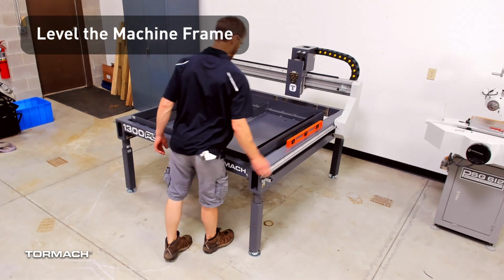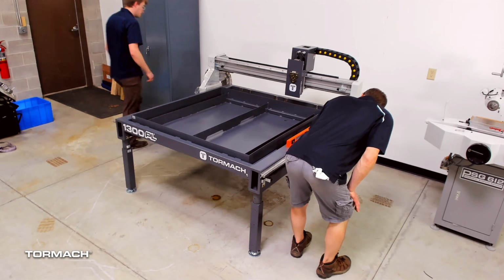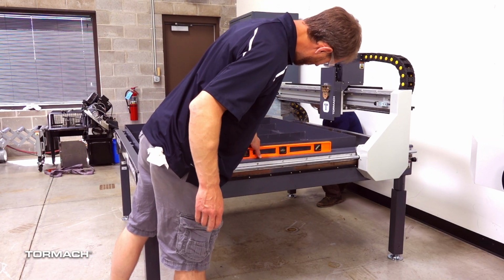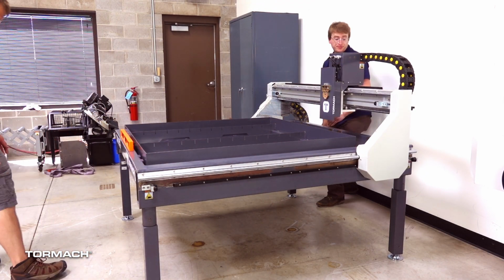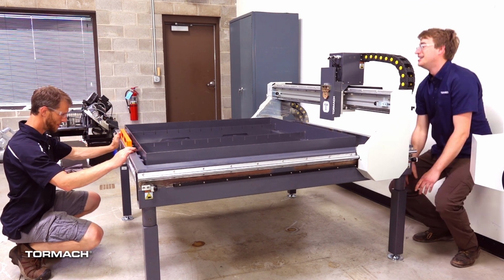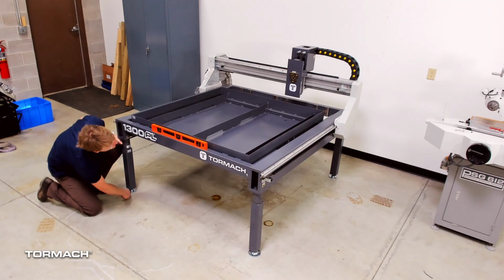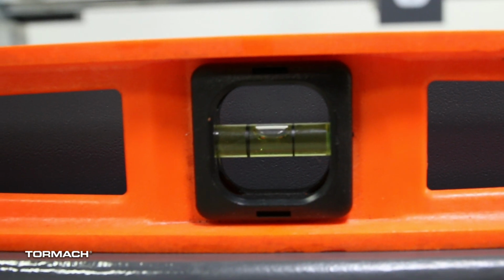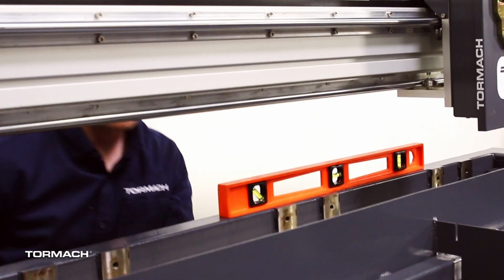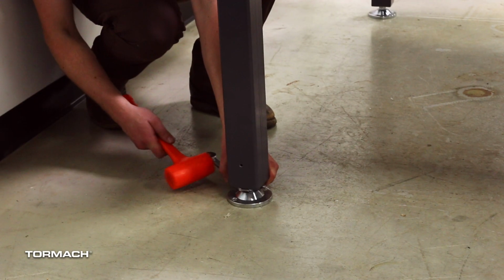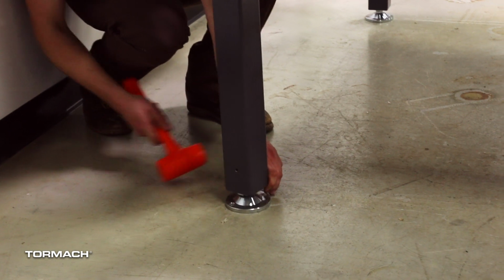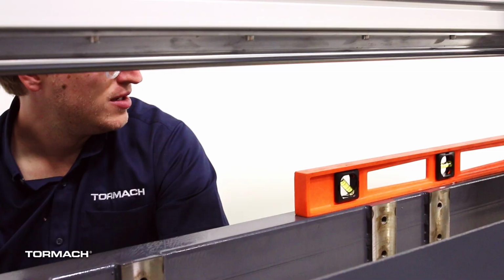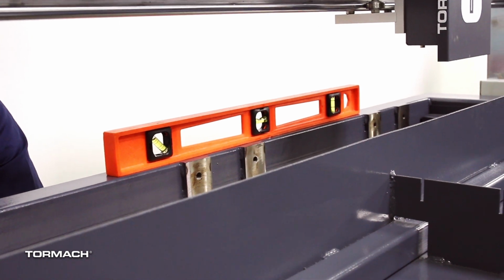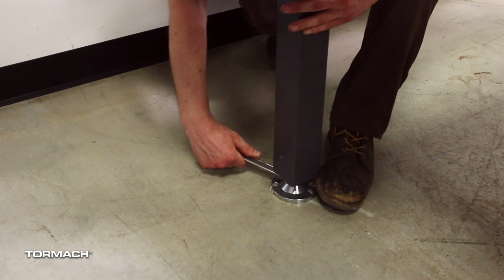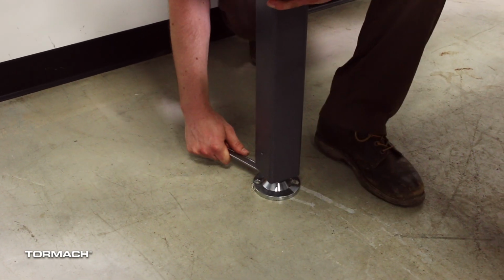On to leveling the machine. We will do this in 2 steps. First, we will level the machine itself, and then we'll level the water table. To level the machine, we're going to place the spirit level in the X and Y directions on all 4 sides of the machine and find which sides are low. We'll use the machine feet to raise up the low sides until everything is level, then verify by placing the level on all 4 sides again. Once this is complete, we can tighten the jam nuts on the feet.